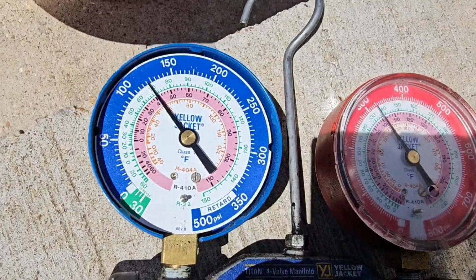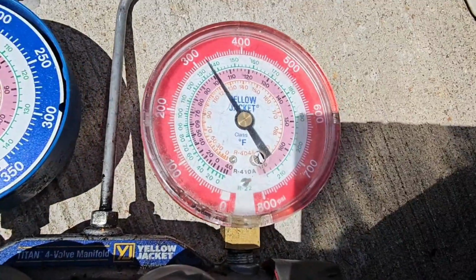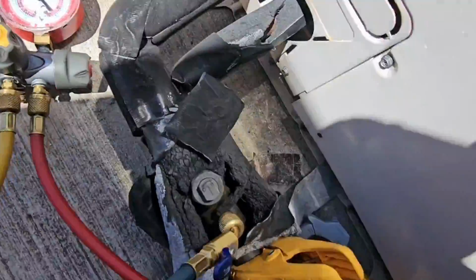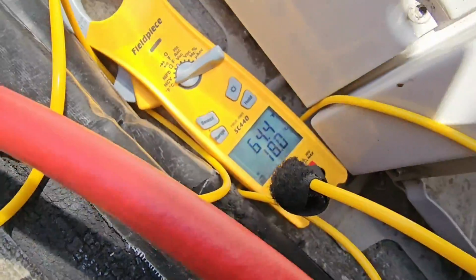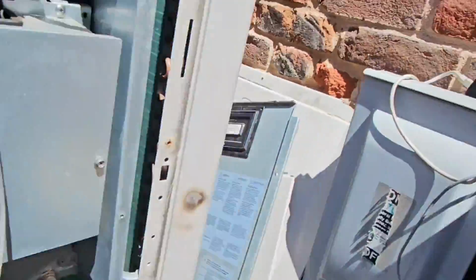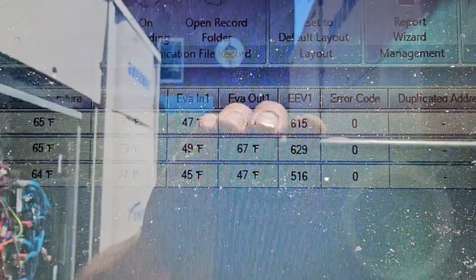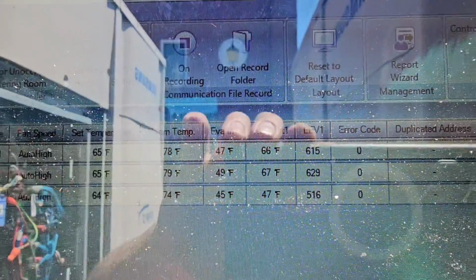After adding some refrigerant, low pressure's 120, high pressure's 320, suction line temperature 64, and then, oh yeah, 45, 47, 49, 67. That is much better. EEV valves are opening up a little bit. I'd say we are close to charged.